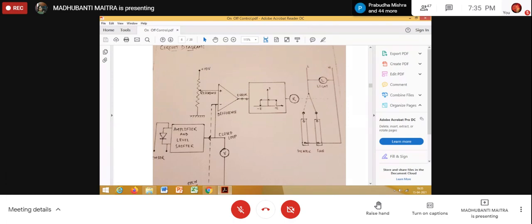And since the band is plus or minus E equal to 5 degrees centigrade, I'm considering the second position, for my convenience only. So this point corresponds to a value which is equal to 70 degrees centigrade, right? Now at this point the temperature will be 75 degrees centigrade, and at this point the temperature will be 65 degrees centigrade. So this is the margin, which is equal to 10 degrees centigrade.